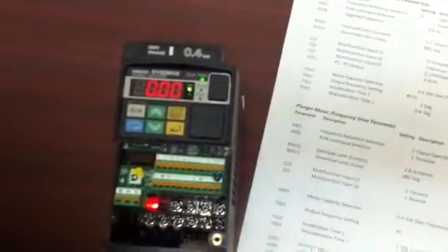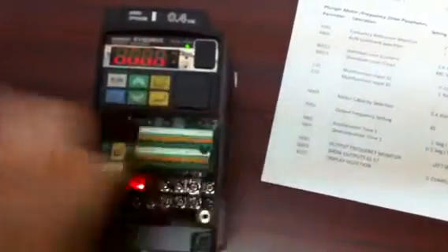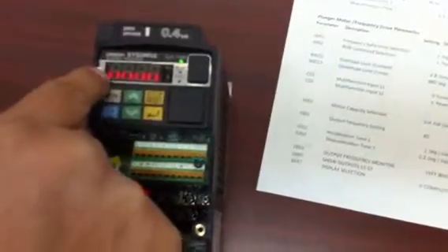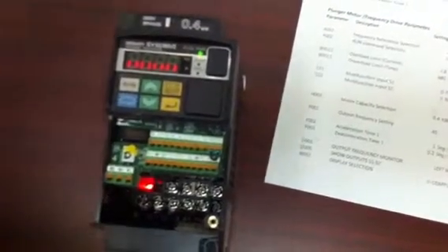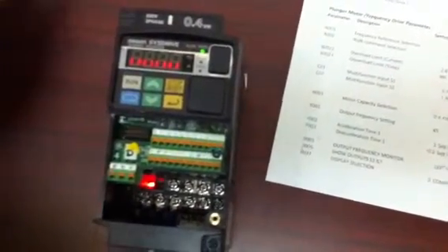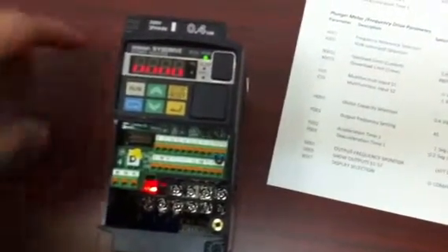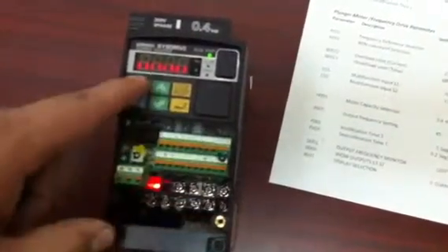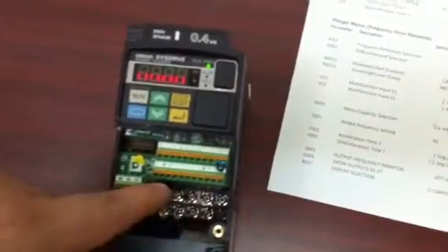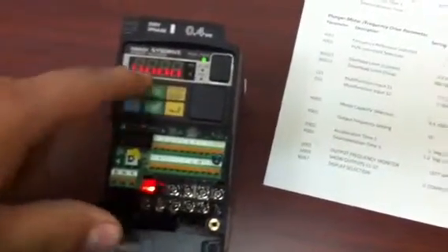If you think you're getting an issue with the PLC sending signals over here, you can also use the parameter D005. What this does is all of the little lines will go up upon receiving the signals. So if you got your frequency drive connected to the PLC, and upon activating the jogging, the run, the forward, the reverse commands, none of these lines move up, that means that maybe there's a short between these connectors to the PLC. This is another one that I added in there for ease. So D005 is going to show inputs.